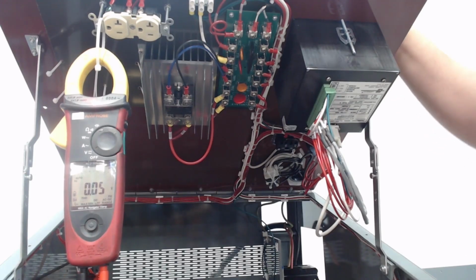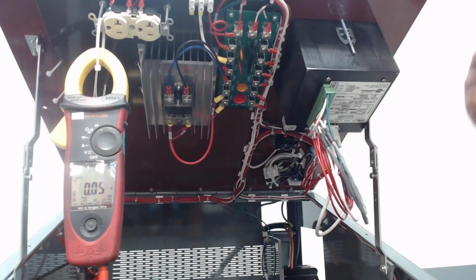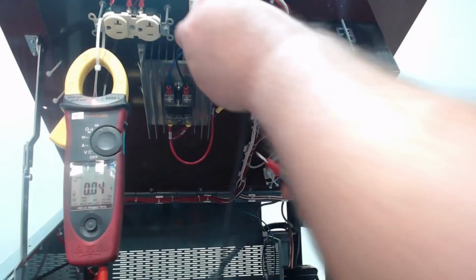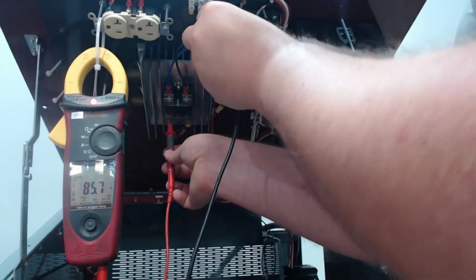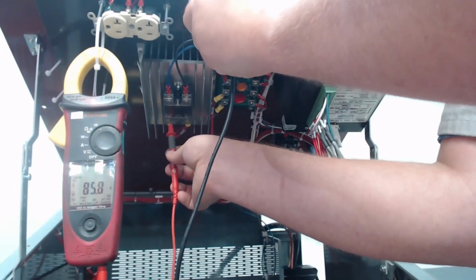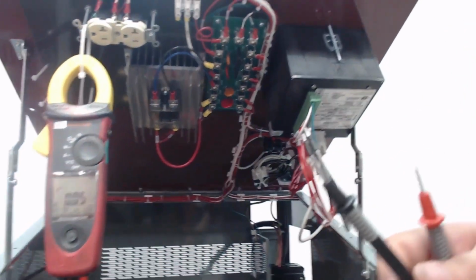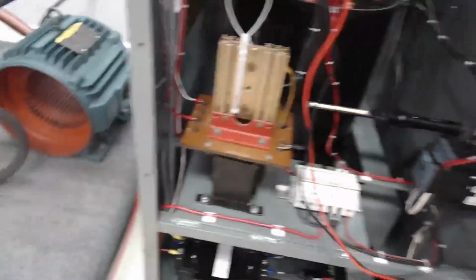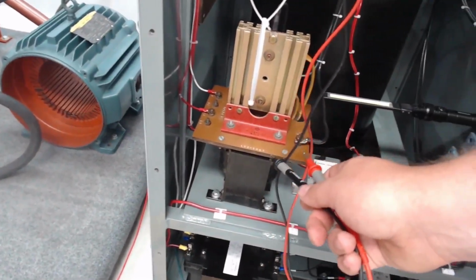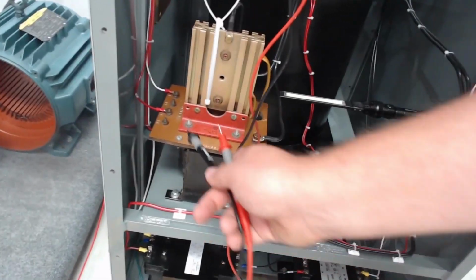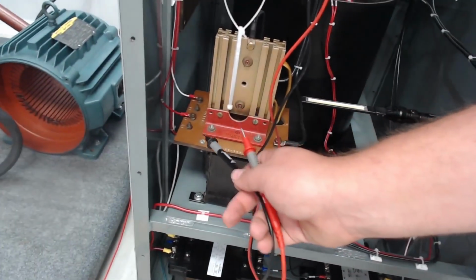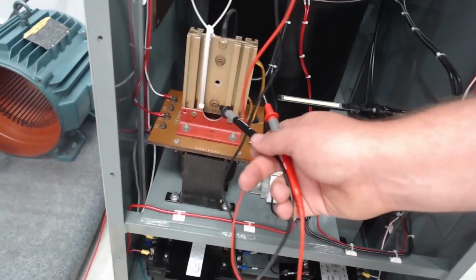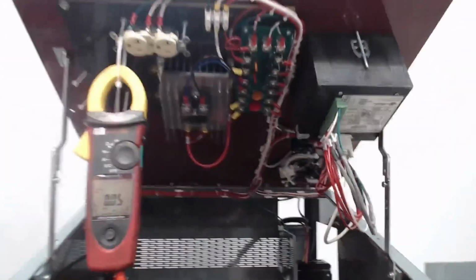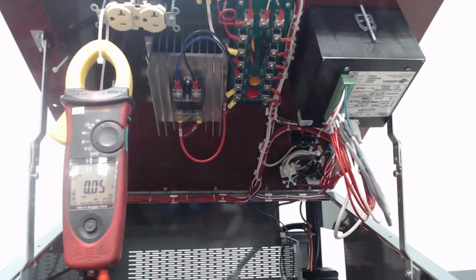So I'm just ramping the unit up to the max it'll do. On this armature, we may not hit full max, but it should be pretty close. So there. Where are we on that? 85. Okay, 85. Not quite there, but close enough. Also, what you can do is on this DC transformer right here, you can check that white and red, and that's going to be that same 85 volts that's coming out going into it. So as that ramps up, that's where that should be going. You can check on that end to make sure you don't have any connection issues or anything further than that.